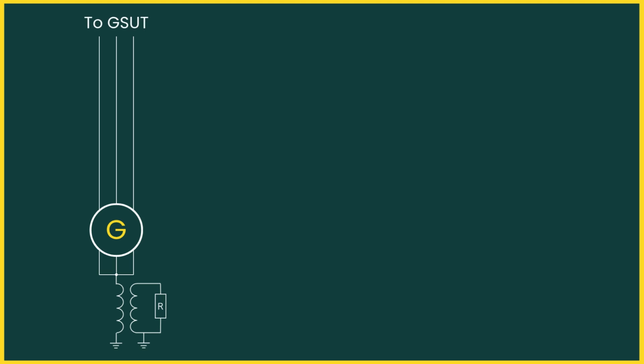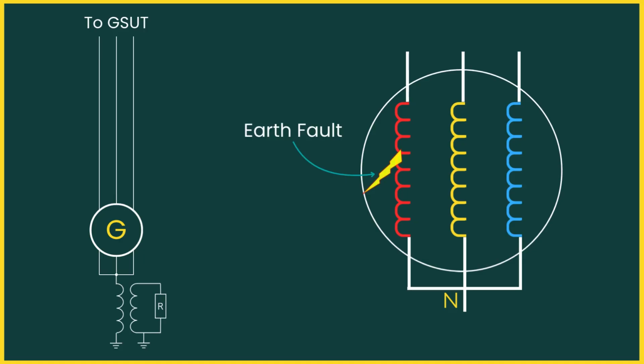In any synchronous generator, the most probable insulation failure is between a phase and earth. That's because of the way stator windings are built. Even a small earth fault can quickly escalate, causing burning of the stator core, mechanical stress on conductors, or even fire in air-cooled machines. Once the core laminations are damaged, the generator often needs to be sent back to works for repair, leading to long outages and high costs.